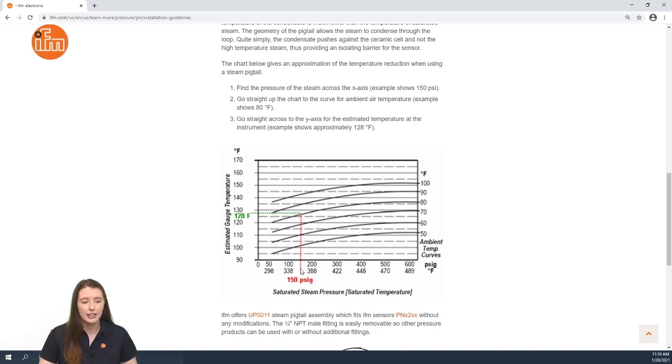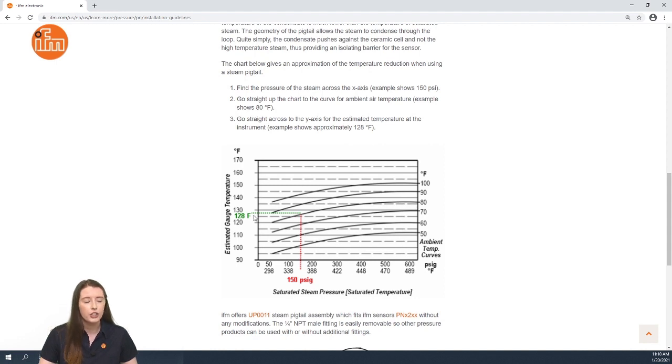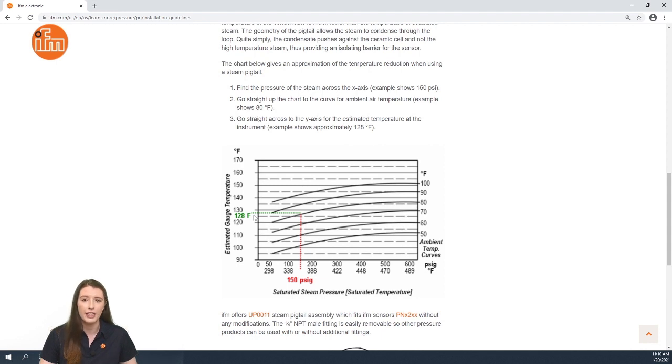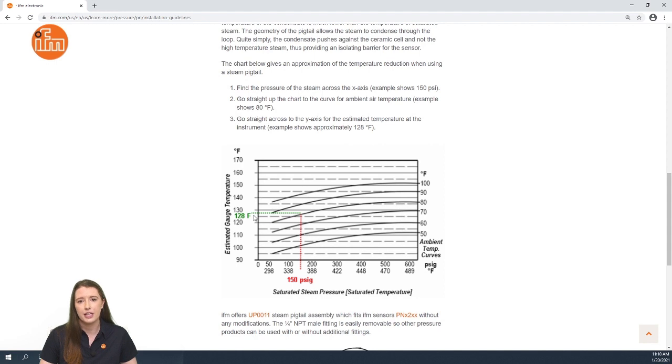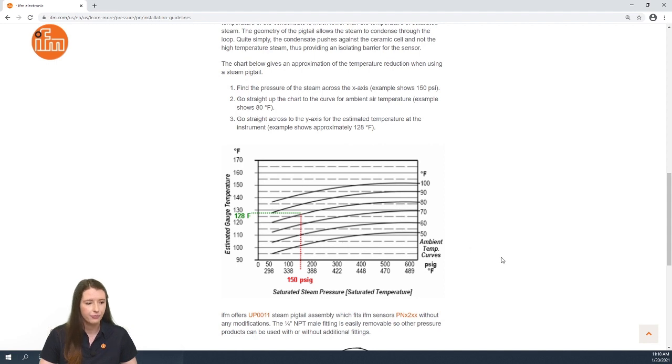you can go to the x-axis of the chart at 150, go up to the curve of 80 degrees fahrenheit, and you can determine that the PN sensor will see about 128 degrees fahrenheit at its measuring cell. So you need to confirm that the sensor can handle that temperature.